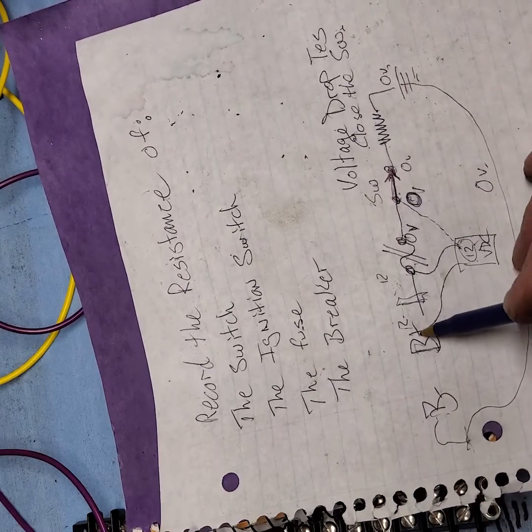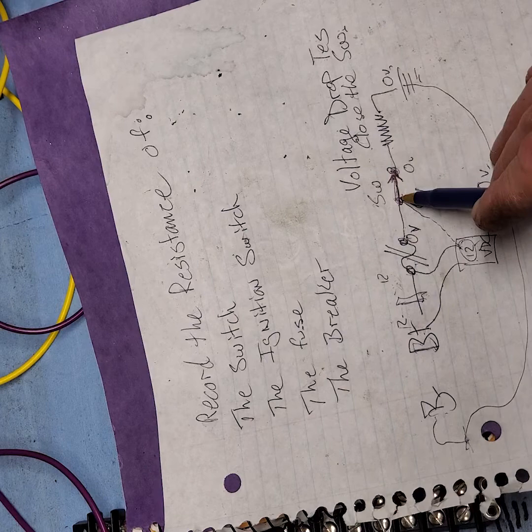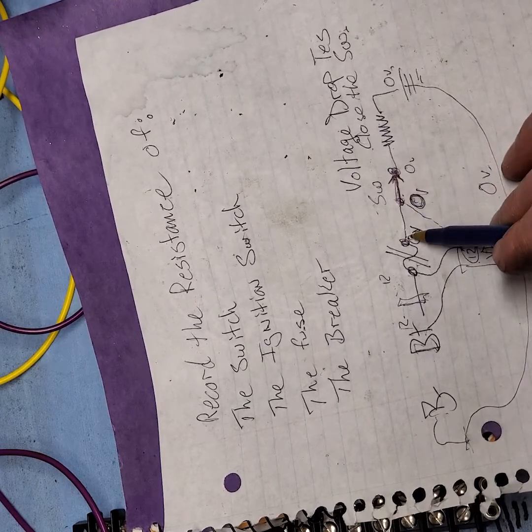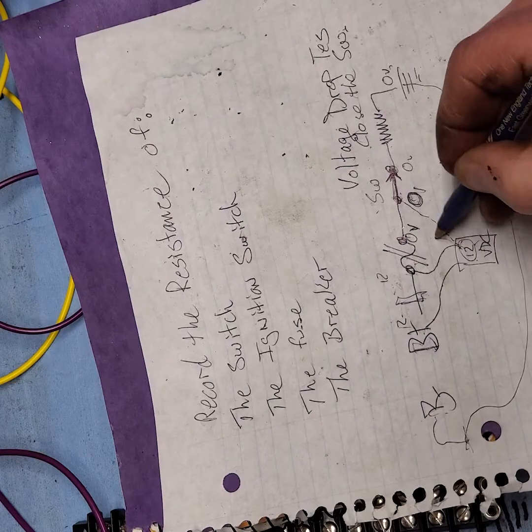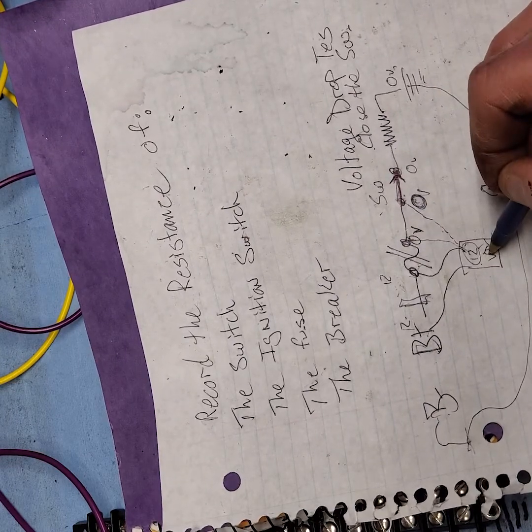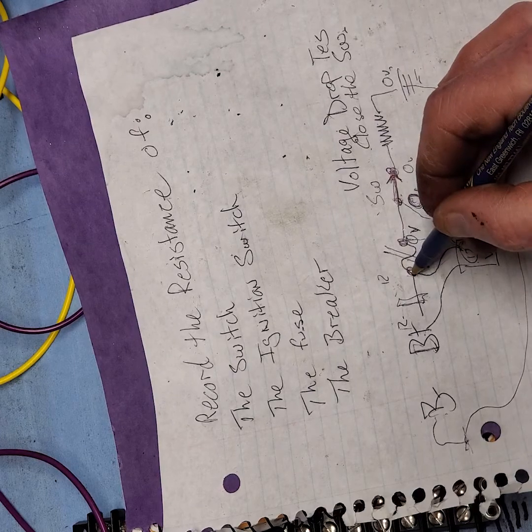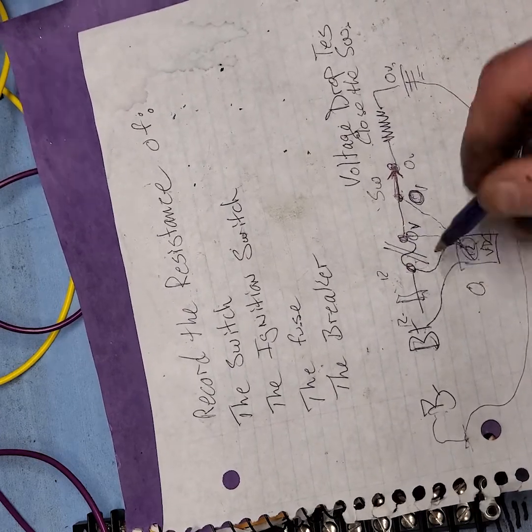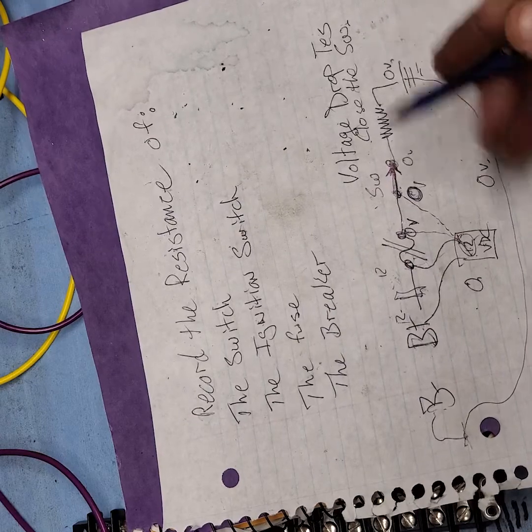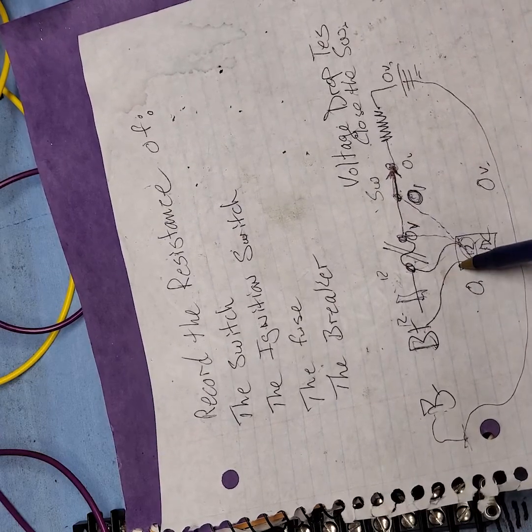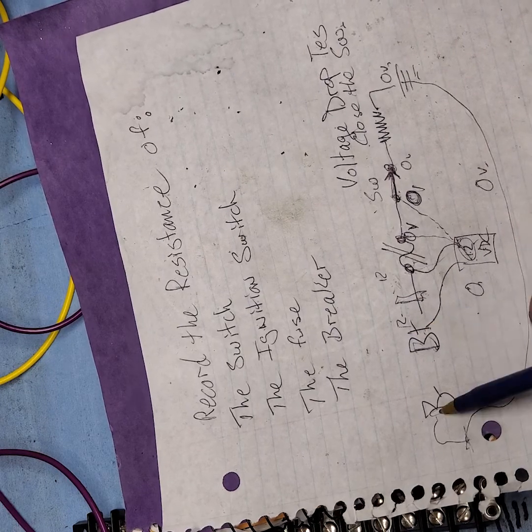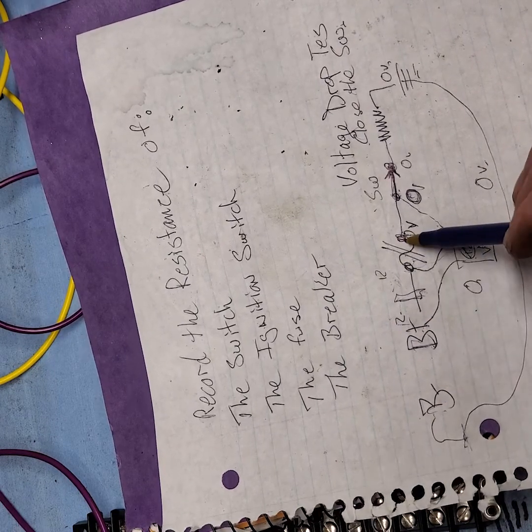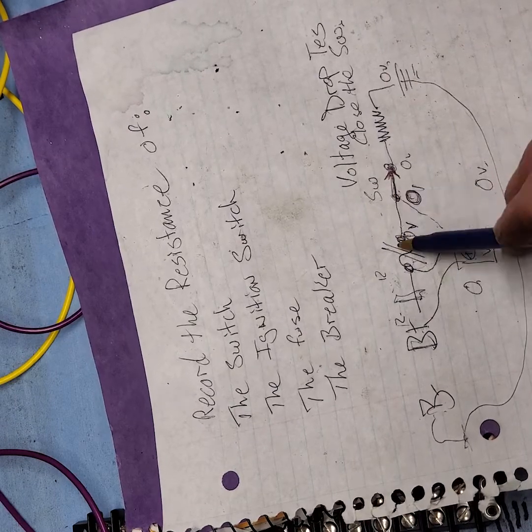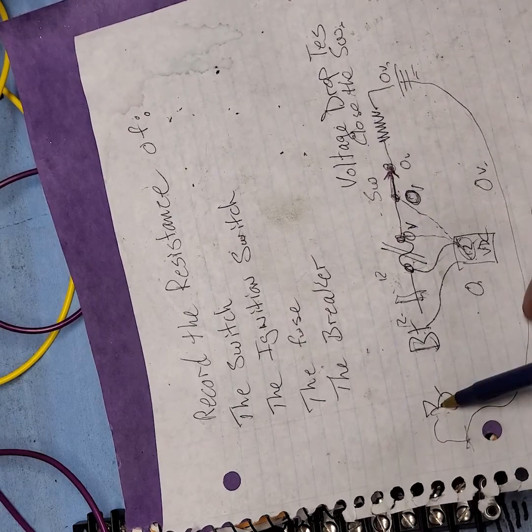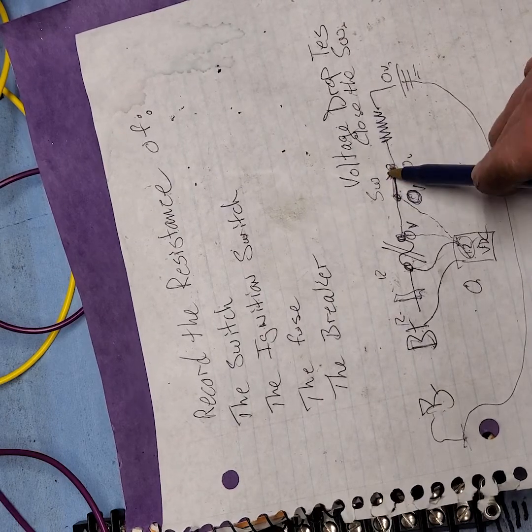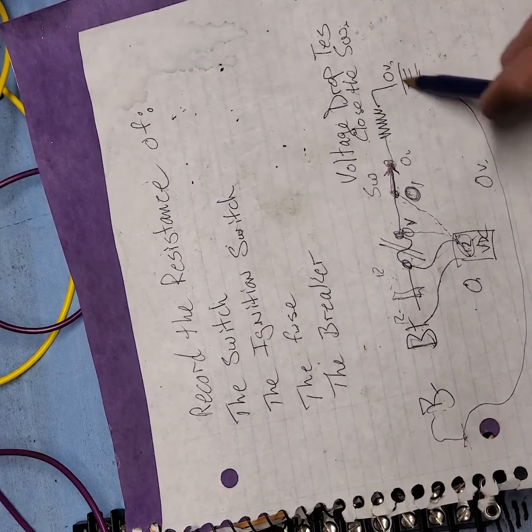That's 100% voltage drop through that circuit breaker. So again, it's a power to a power position. So if I back up and I go to that breaker, I'll bring my meter lead back to the breaker and I'll still read 12 volts. As soon as I go to the other side of the breaker, my meter will go to 0 volts because 12 minus 12 is 0. Another way you can do it is you could take that meter lead and you could put it on ground. And then you would suspect that you should have voltage here before the switch, and you would read 0 because it would be 0 minus 0, and so on.